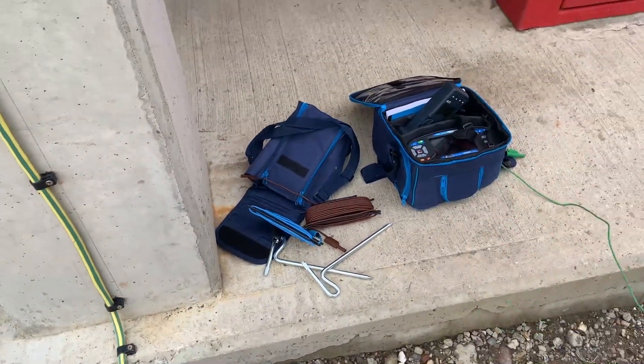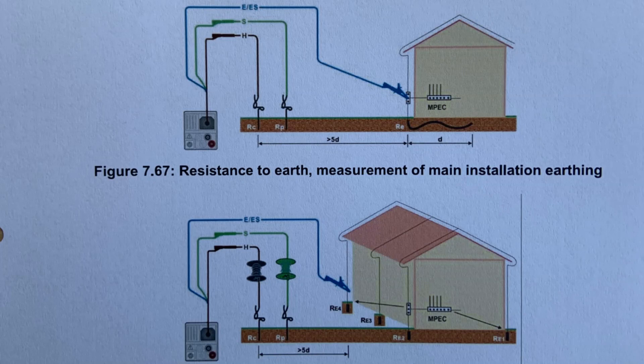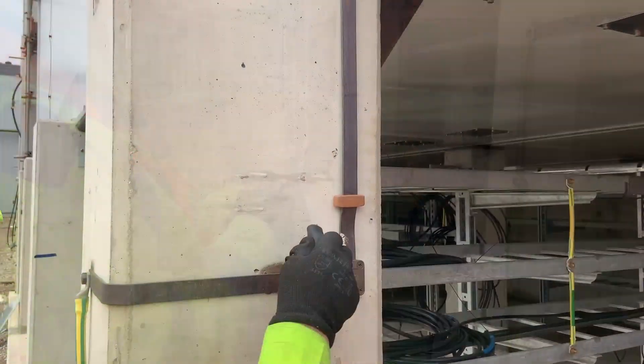Next we set up the Metrel multifunction tester. The test this one does is a 3-wire connection. The blue connects to the earthing point, the brown connects as far away from the installation as possible, and the green point connects in between the two.